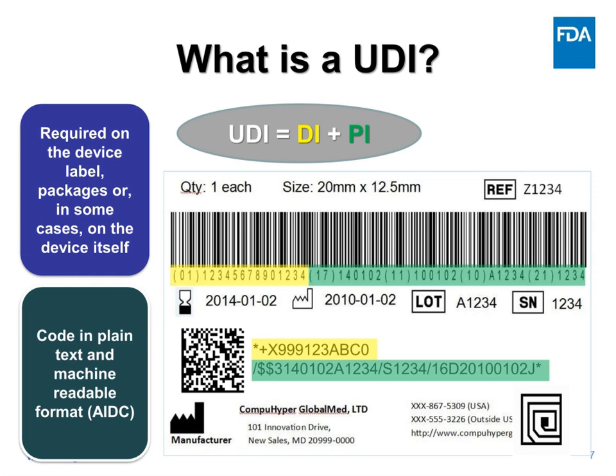So the top line, that is a single line barcode, is the GS1 format, and you can see in yellow that the DI up in the UDI equals DI plus PI. That stands for device identifier and production identifier. The device identifier is in yellow in both of the representations of UDI, and the production identifiers are in green. And if you can see, there's patterns here.